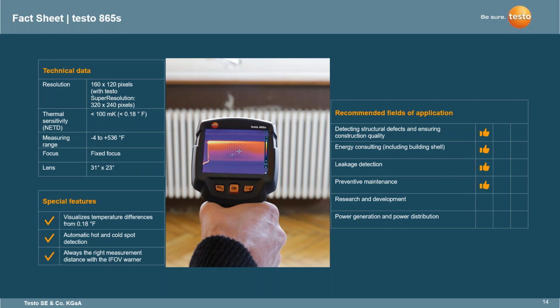As you can see, the little round piece within the imager on this screen, with the IFOV warner on there, you're actually able to get a more accurate depiction of what that temperature is because of the way that the pixel size is captured. As opposed to taking things from outside, because it may not have as many pixels outside that little square, you're able to get a more focused reading on what that temperature is to be able to determine the differences.